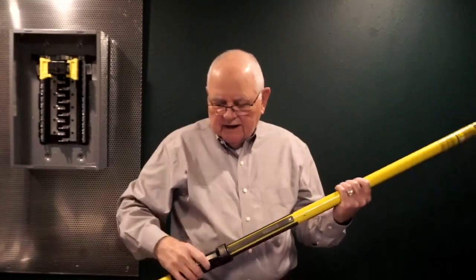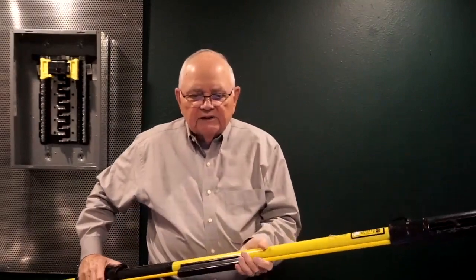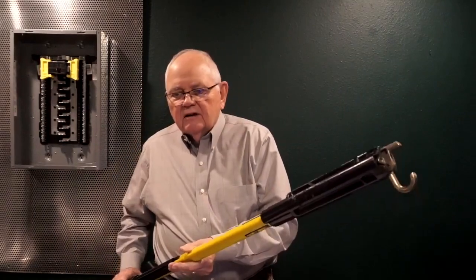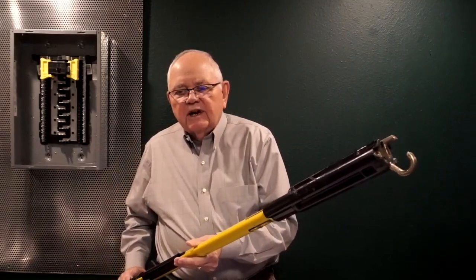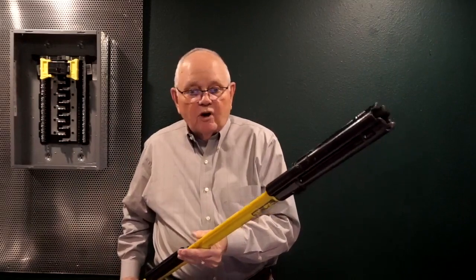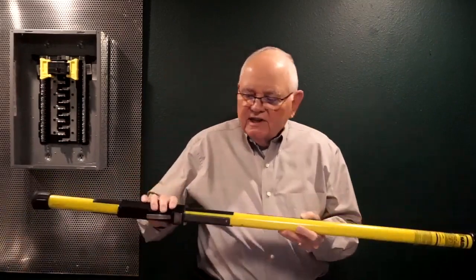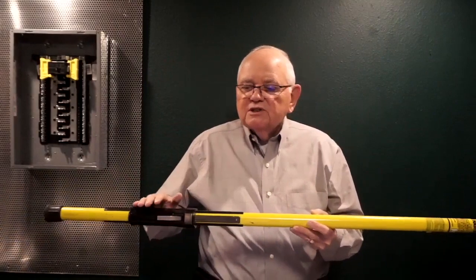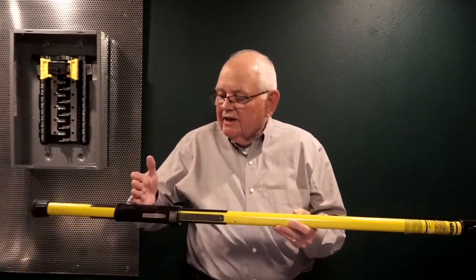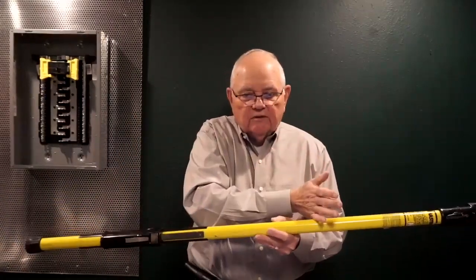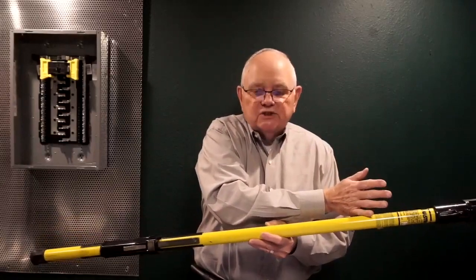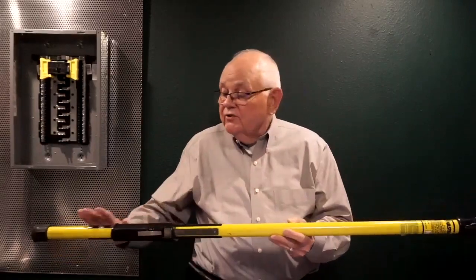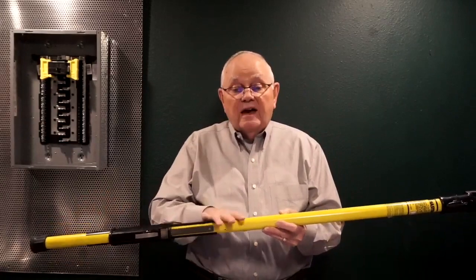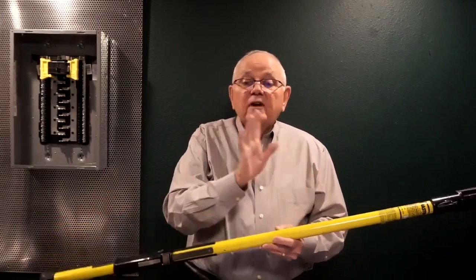It's got a handle down here, and I can slide the handle back and forth, and as I do, that comes out and opens up on the end, a hook, and I can hook onto something and do some work. Now, the reason I point this out, this is insulated. When this is manufactured, it is insulated at 100,000 volts per foot. That's a lot of insulation. We test it every 2 years now at 75,000 volts per foot. So there are a lot of tools out there that can give us a lot of protection.